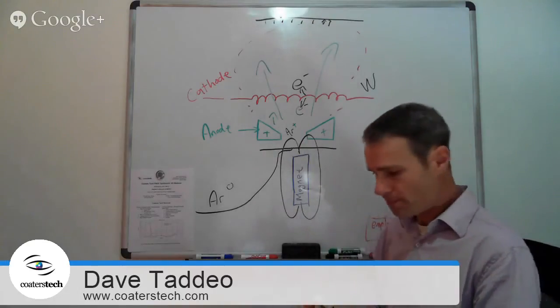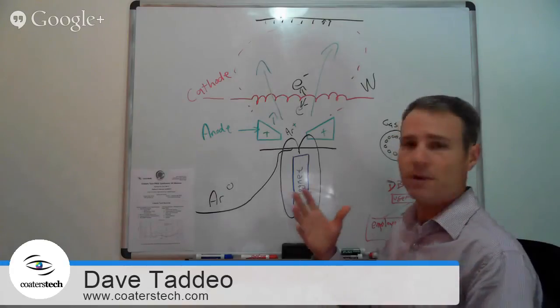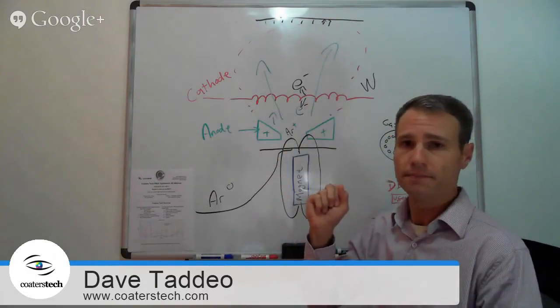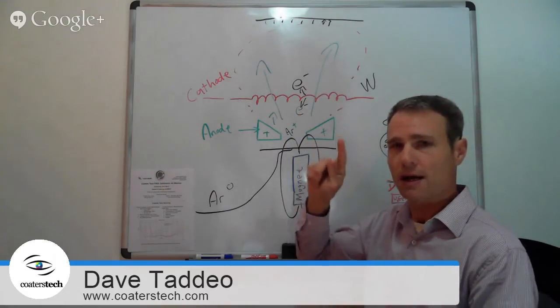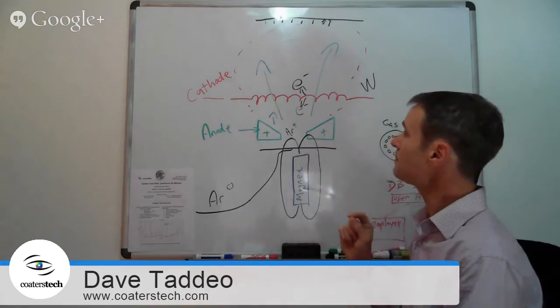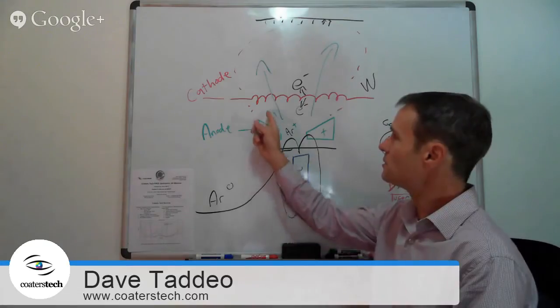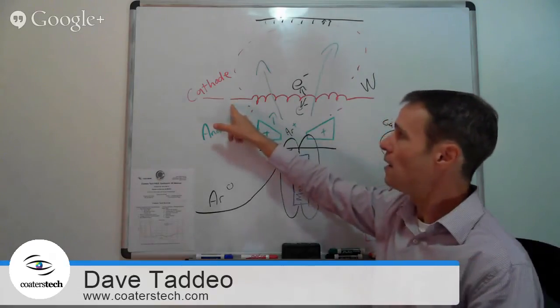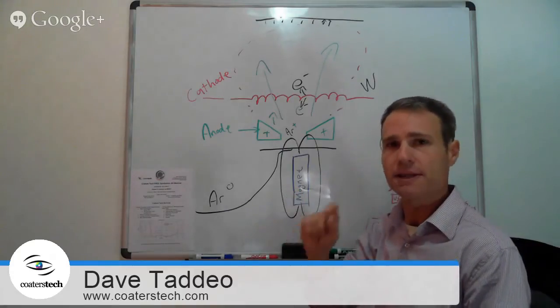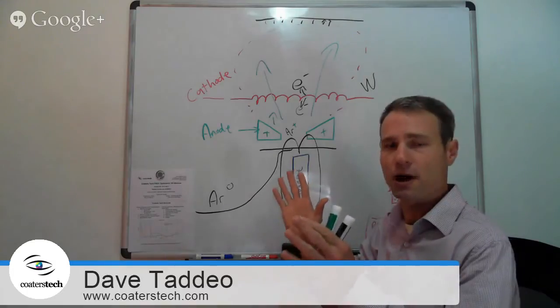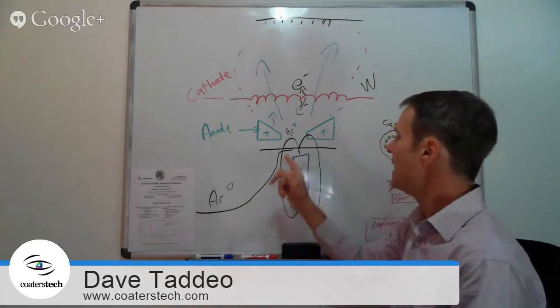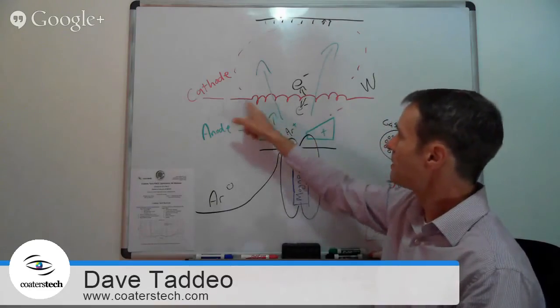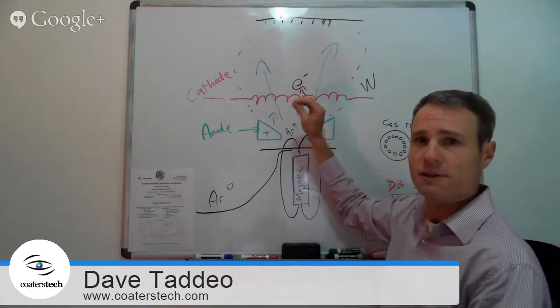One thing to take note of is that in some instances you will see on the metal tooling, when you take the parts out of the coating machine, some arcing or sparking marks that look a little bit like lightning where the coating is. What that means is there's too much charge — it's not being bled away. Our cathode will also act as a neutralizer. You'll see that setting in the software or on the actual ion gun controller: there's a neutralizer current. As our argon ions accelerate away from our anode, our cathode will pick some of that up and close that voltage gap.